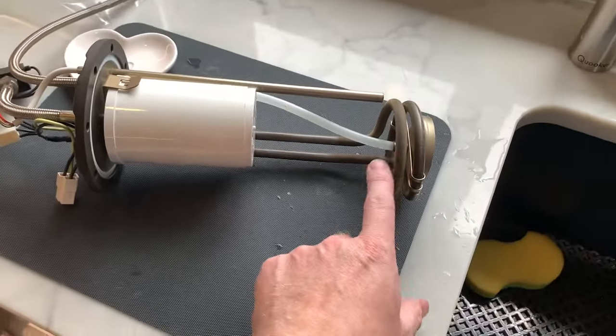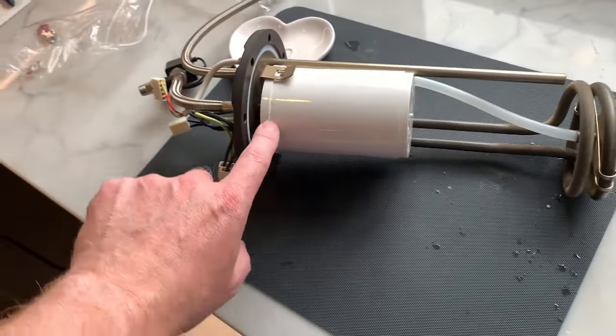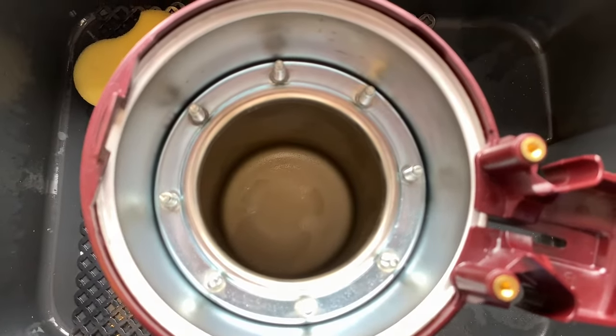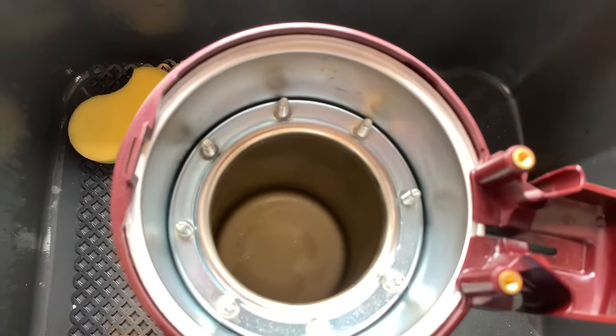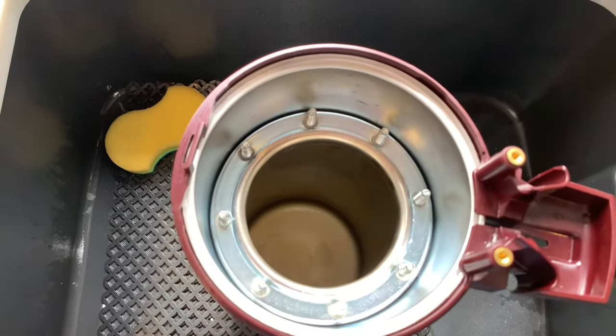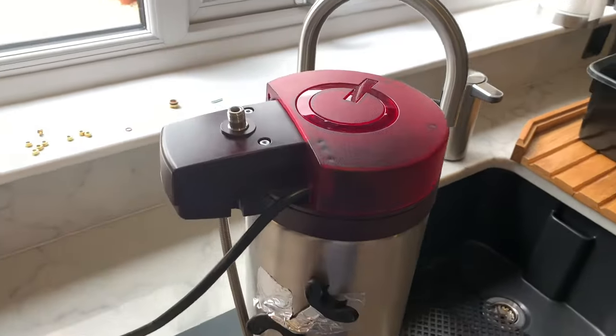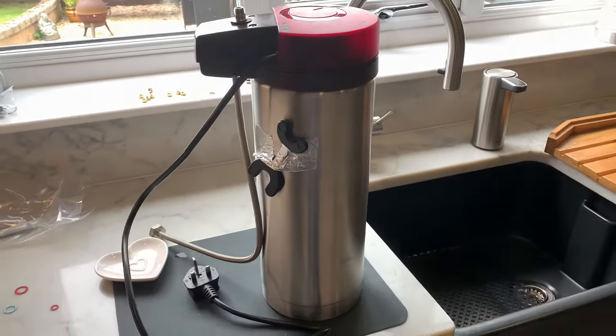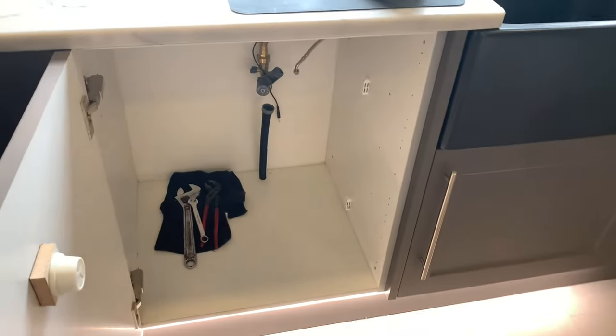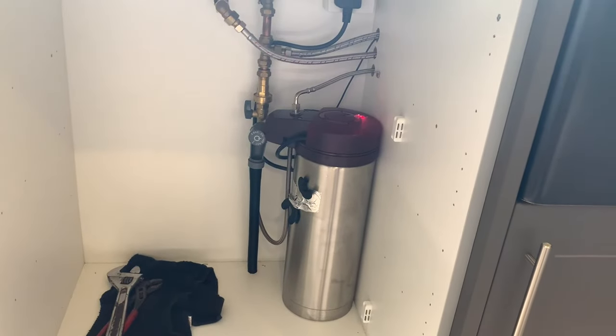Okay, that's the heating element all cleaned up, tubes all cleaned up, new filter installed, new gasket put on. This just came up nice — there's no staining in the bottom of there, it's all nice and smooth. Cleaned up the sealing surface as well for the new gasket. So we'll put this back together and see how it performs. That went together a lot easier than I thought it would — absolutely no problems, everything's snug.